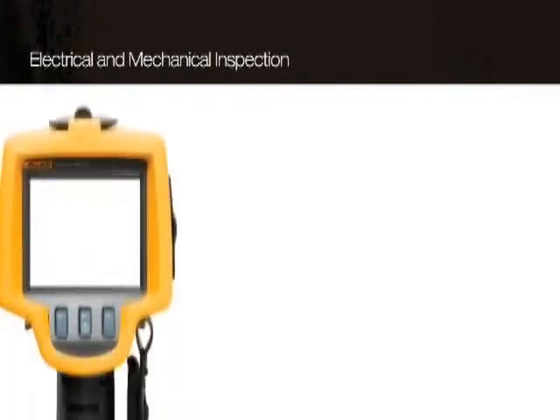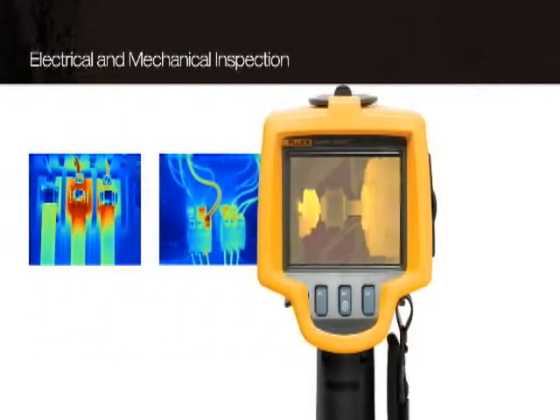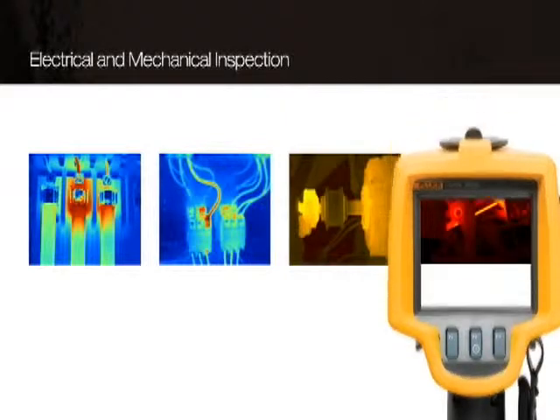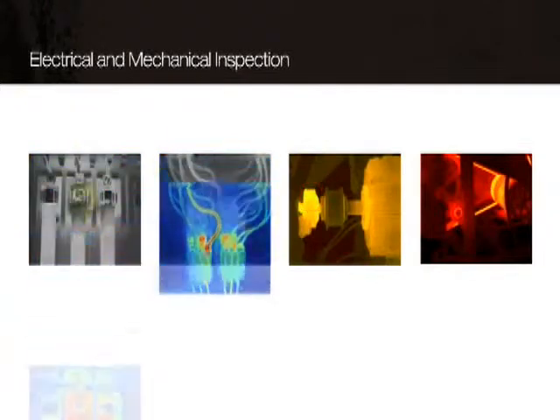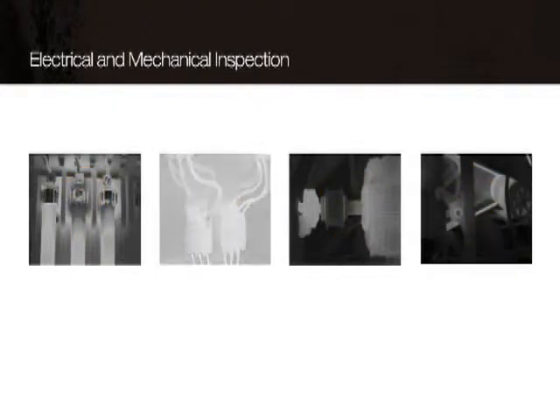For example, let's say you're performing an electrical or mechanical inspection. Using the thermal imager, you can take infrared pictures of fuses, connections, couplings, and misaligned belts. The IR image will reveal hot spots in the system, verifying problems like unbalanced and excessive loads, loose connections, or misaligned parts. Without the thermal imager, problems may go undetected and you might assume systems are working properly.